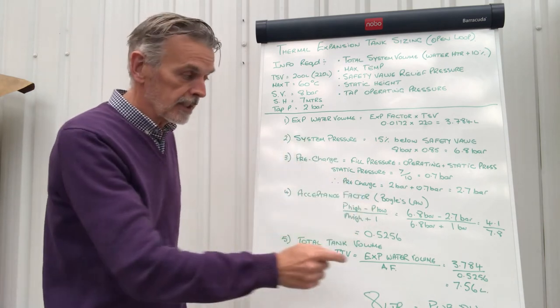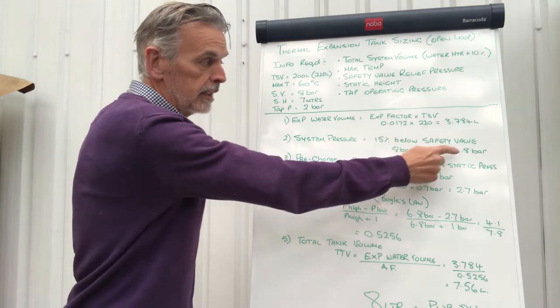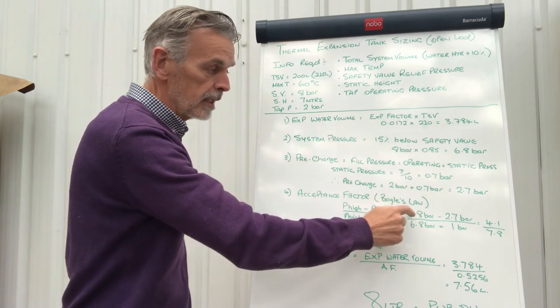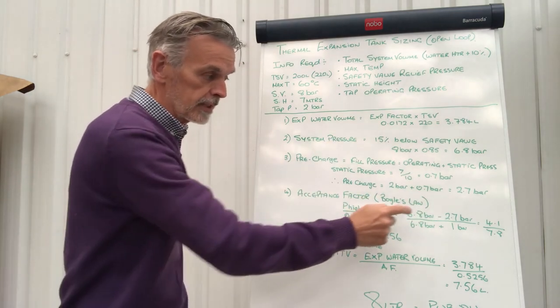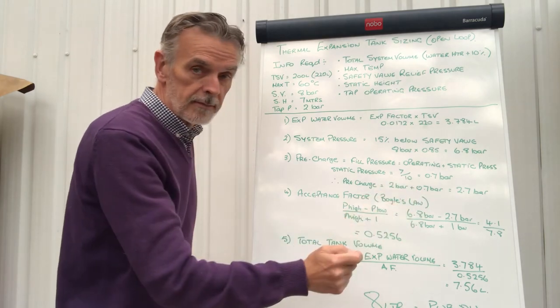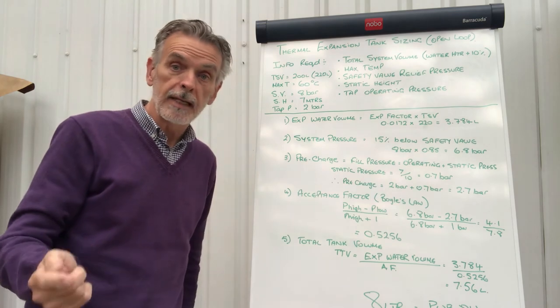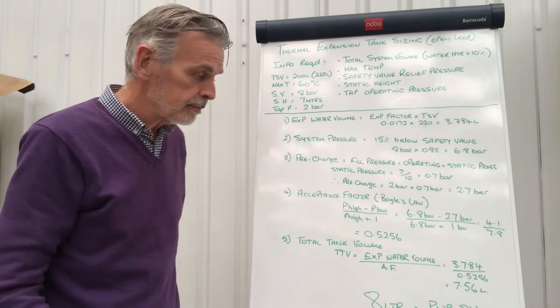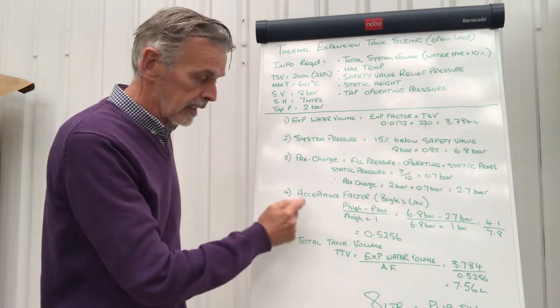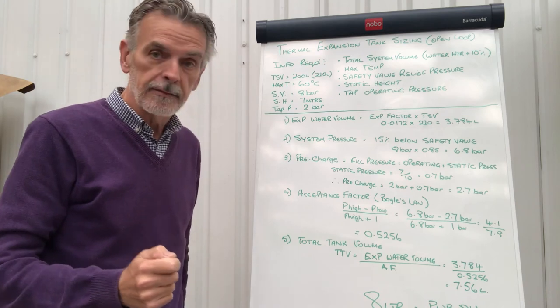Now Boyle's law states: high pressure P high minus P low divided by P high plus 1. So in this calculation again, we have a high pressure of 6.8 bar, which is here, the system pressure. We have a low pressure of 2.7 bar, which is the pre-charge. So 6.8 minus 2.7 bar divided by 6.8 bar plus 1 bar, 1 bar being atmosphere. That comes to 4.1 divided by 7.8 bar. That gives you an acceptance factor of 0.5256.